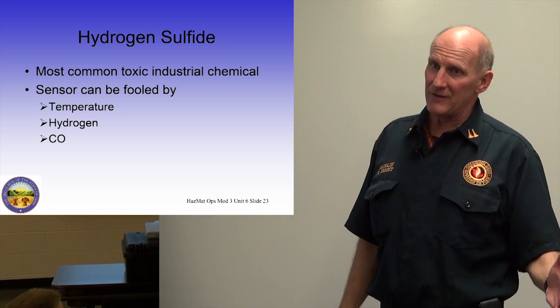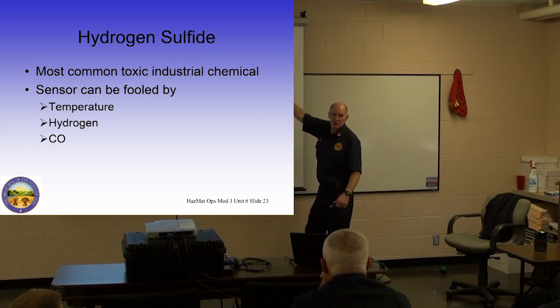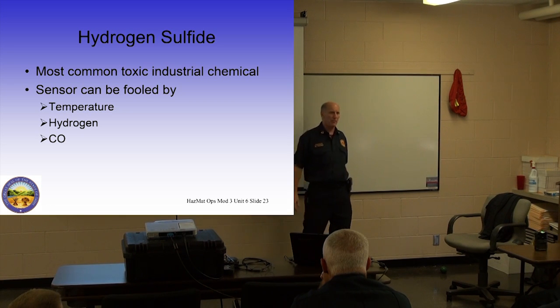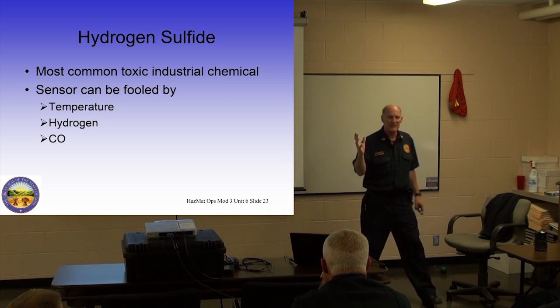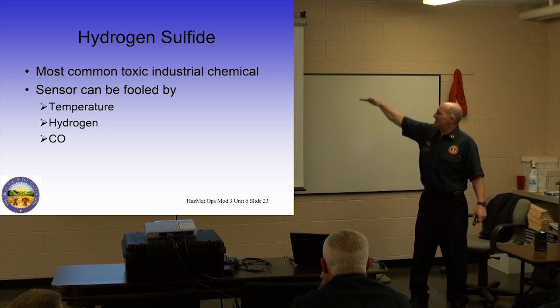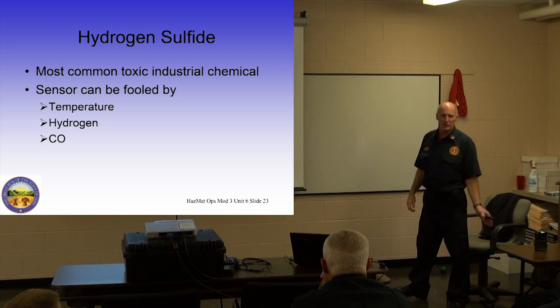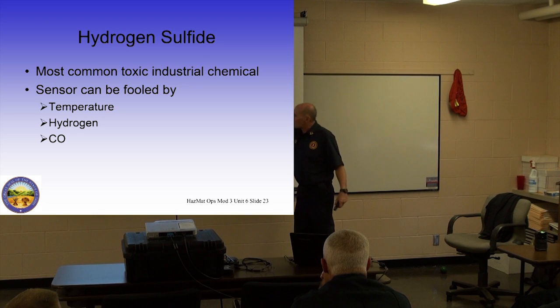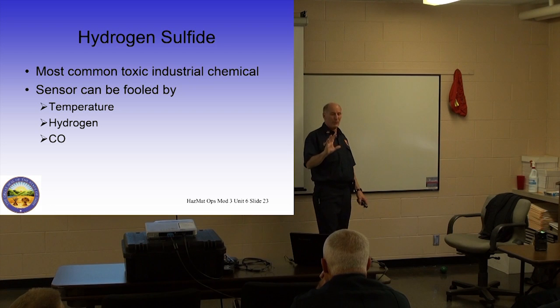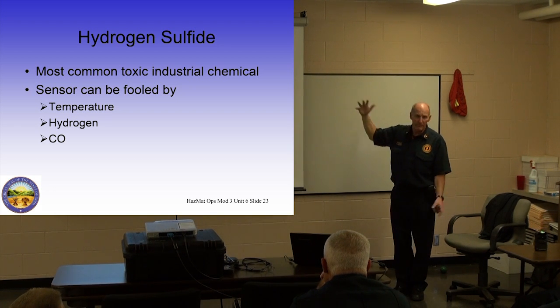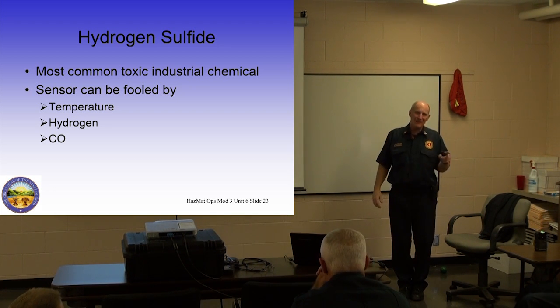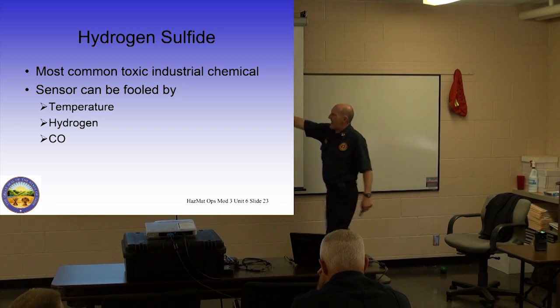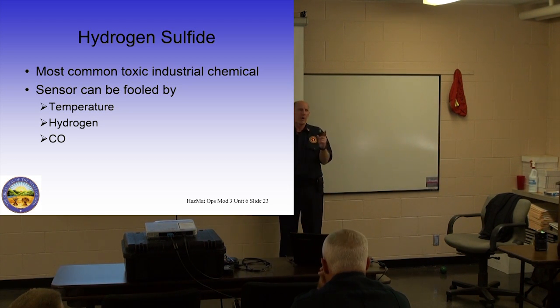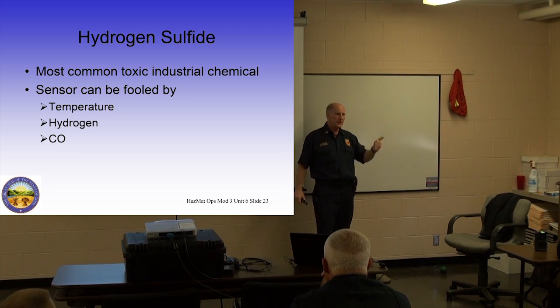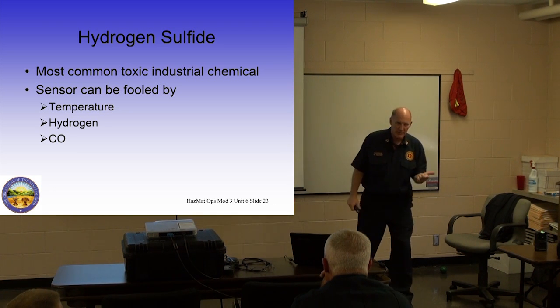Hydrogen sulfide is the second most common hazard in business or industry. It's the most common in a sewer system, and the most common anytime you get a long-term fuel or diesel leak. So that's why it's also included. It's an industrial chemical we want to worry about, but just remember the hydrogen sulfide sensor can be fooled by temperature, by the presence of hydrogen, and by the presence of carbon monoxide, and this is not an exhaustive list. There are other chemicals that will fool the CO and H2S sensors.